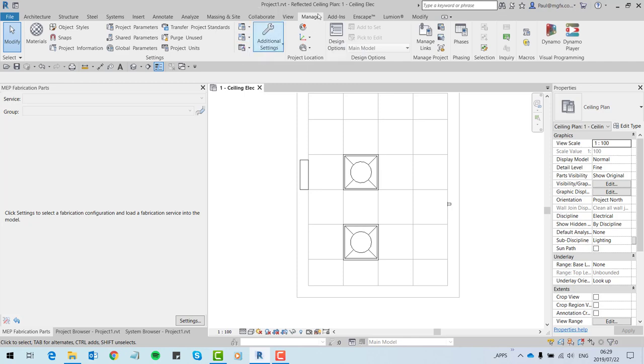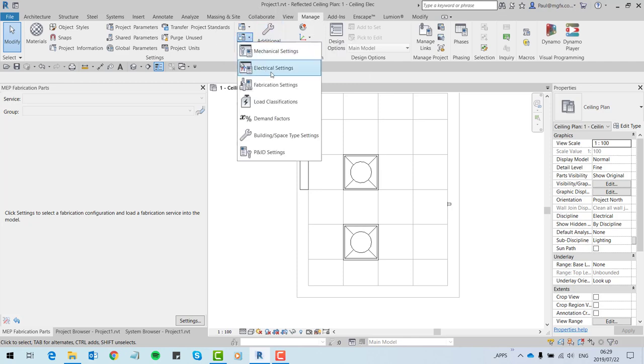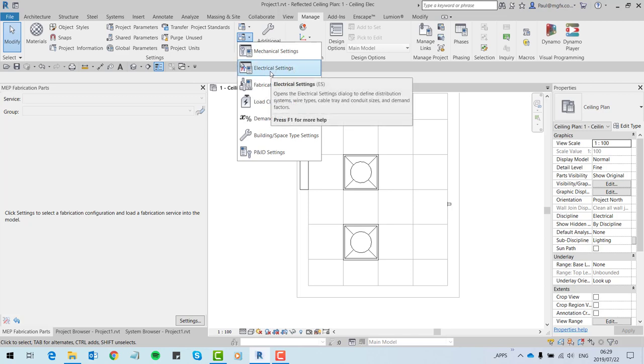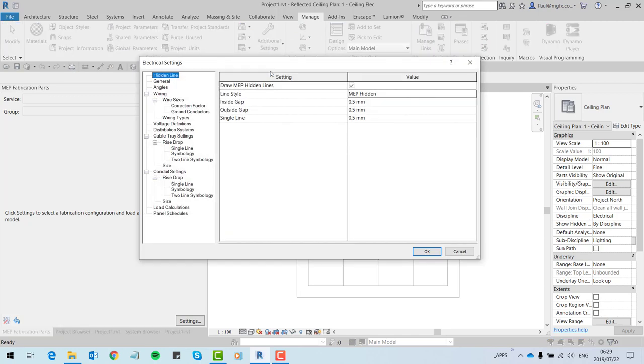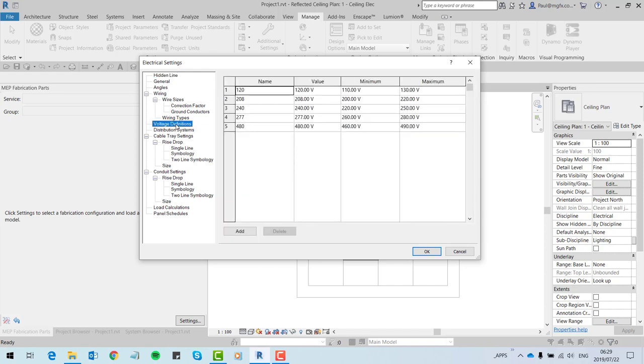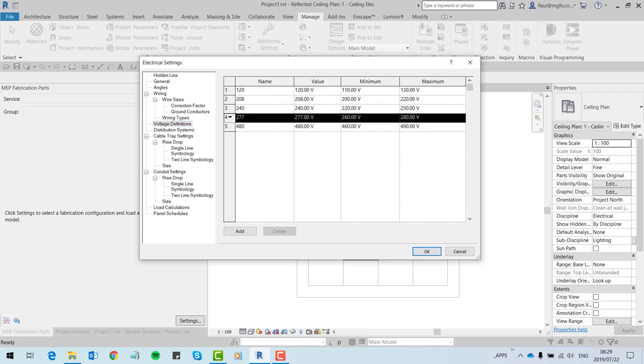To understand this better, let's have a look at the electrical settings. On the Manage tab under the MEP settings, there is our electrical settings. Firstly, the voltage - here we have the 277 voltage definition. The nominal value is 277, the minimum 260, and the maximum 280. Because 240 does not fall within the range of 260 to 280, it is rejected.